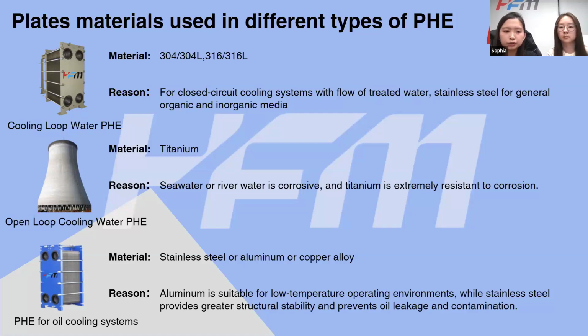So the material used for the open loop cooling water system is titanium, because open loop cooling water systems usually use seawater or river water, which is highly corrosive. Titanium is chosen for its extreme resistance to corrosion, which can effectively prevent the damage caused by corrosion and ensure the long-term stable operation of the plate heat exchangers.